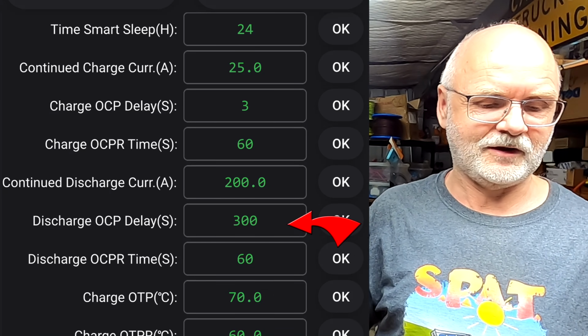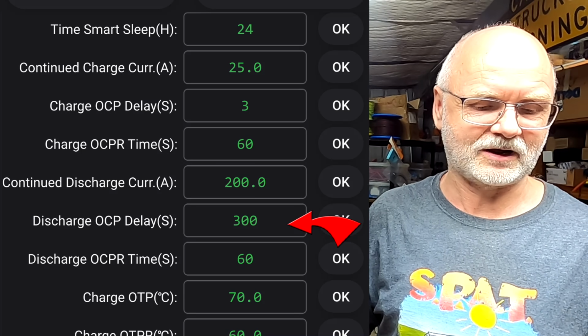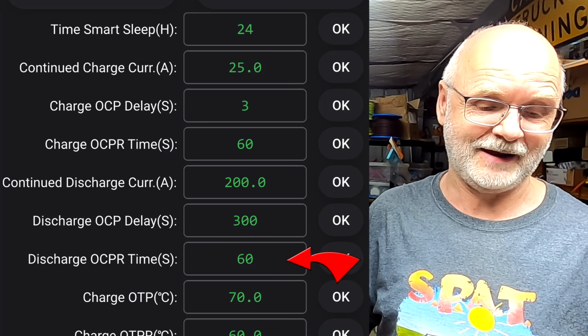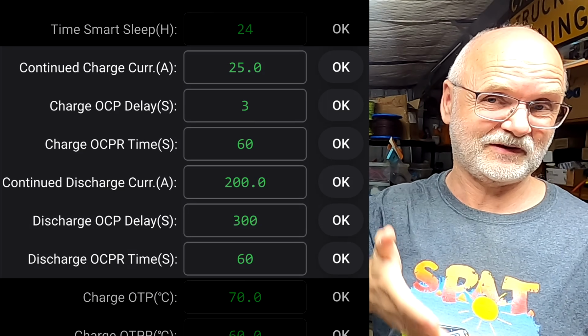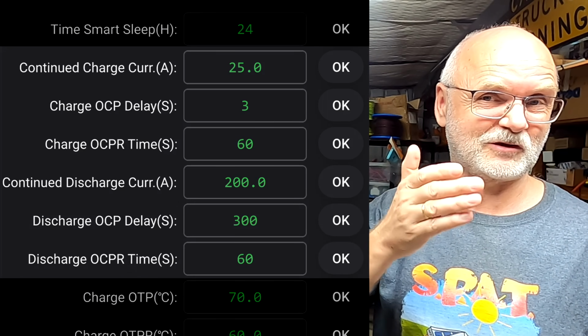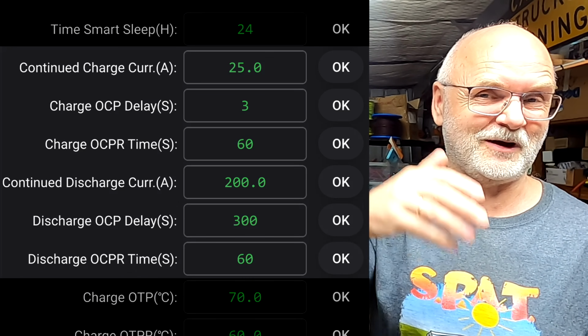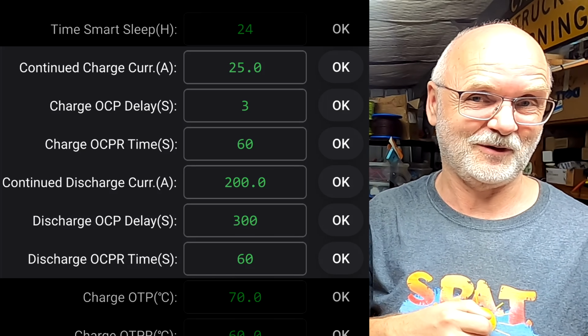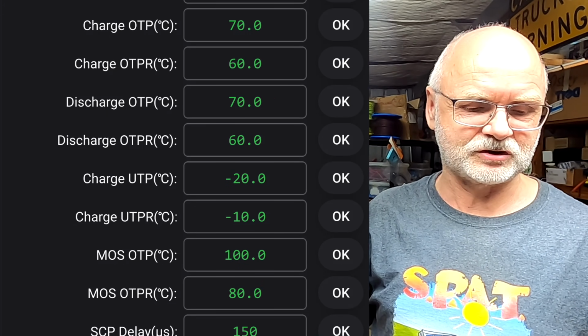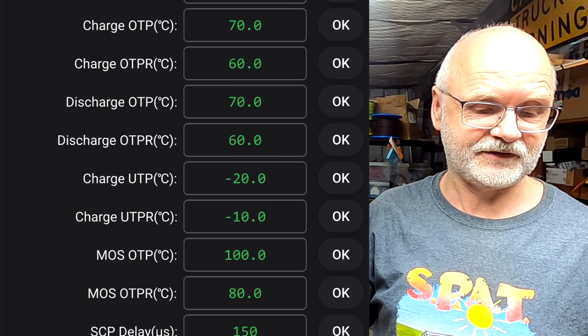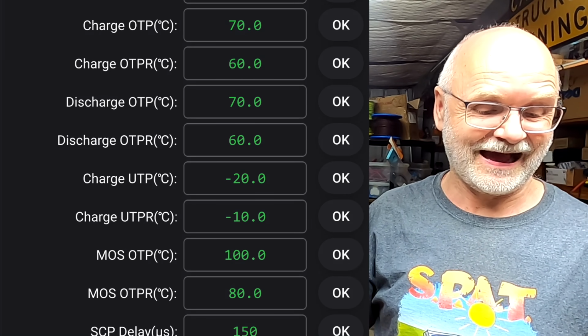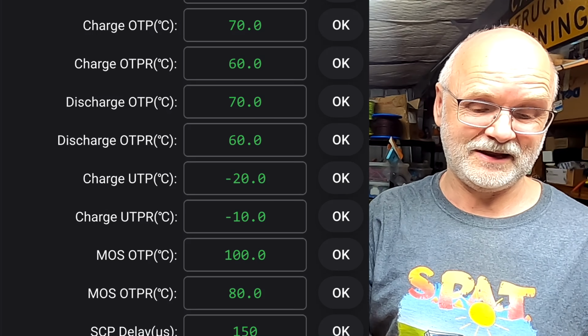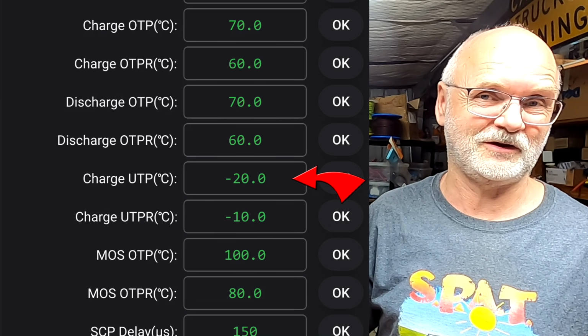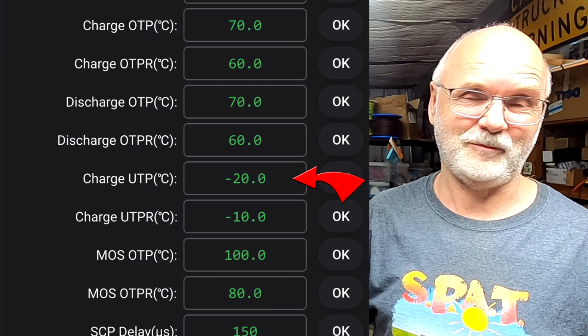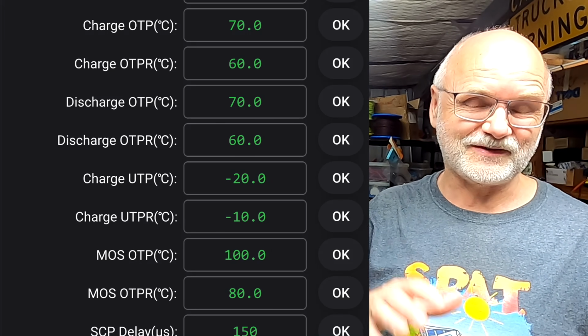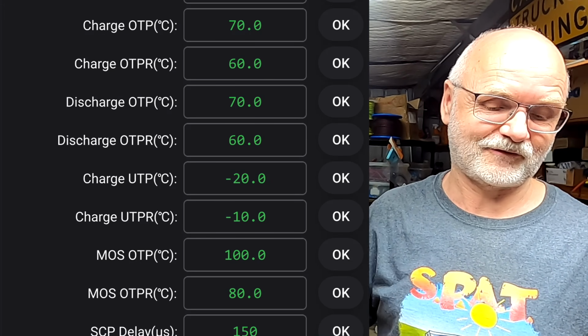And here as well, we've got an overcurrent protection delay and an overcurrent protection recovery time we can set. You can see all these 6 last parameters, they're all nicely grouped. So I would like to see this one for the voltages further up as well. We then have the usual temperatures: the charge over temperature, the discharge over temperature, the charge under temperature, which I told them already is wrong. It shouldn't be minus 20 degrees. You should not charge your lithium battery in negative temperatures at all. So these are some minor bugs they need to fix in the next firmware update.